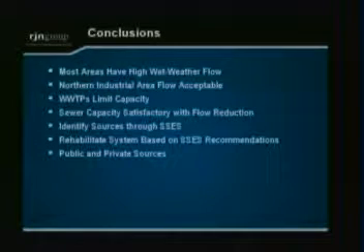One really good piece of news coming out of this, and I really want to reiterate how good this is: your sewer capacity is very good. I can tell you right now, we're working with a few communities around you that do not have that, and what we're recommending to them is relief sewers, which are very expensive. I'm not recommending any of that going forward for your system, which is very good. That's a tremendous amount of savings. But you do have high flow, so we do need to focus on finding the sources where that flow is getting in and trying to eliminate it over time.